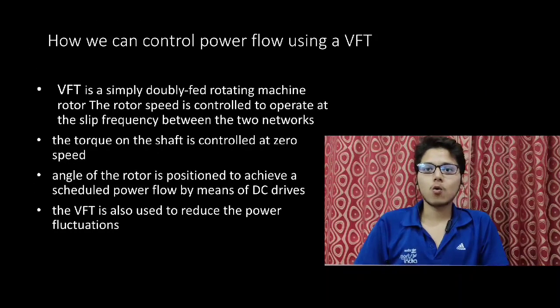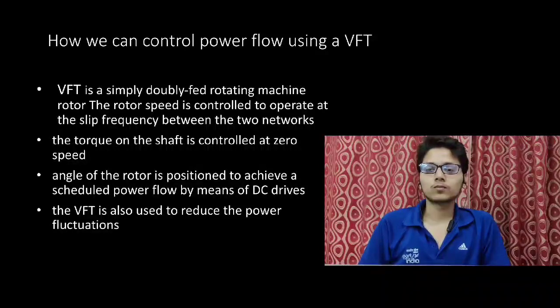Now the question is how we can control power flow using a VFT. A VFT is simply a doubly fed rotating machine which is connected to the involved asynchronous networks to achieve its function as an asynchronous tie between the two networks. The rotor speed is controlled to operate at the slip frequency between the two networks. When two networks with the same frequency are connected, the torque on the shaft is controlled at zero speed. The angle of the rotor is positioned to achieve a scheduled power flow by means of DC drives.